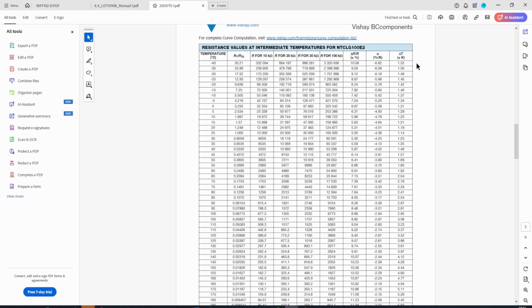Of course, if you've got a lab and a dry well or dry block calibrator and a super duper 0.01% accurate thermometer, then you could do this yourself. A couple of points, 0 and 100 centigrade, are very easy to get, but you're going to need at least 4 or 5 points in order to calibrate your thermistor. Manufacturer's data is definitely the way to go.